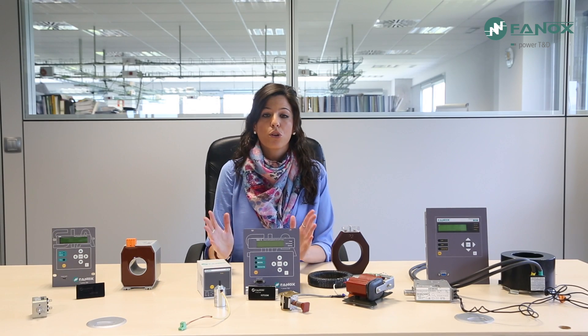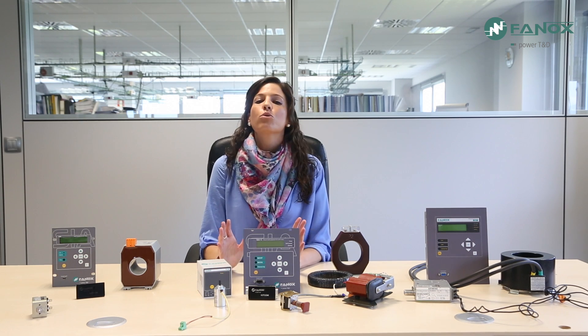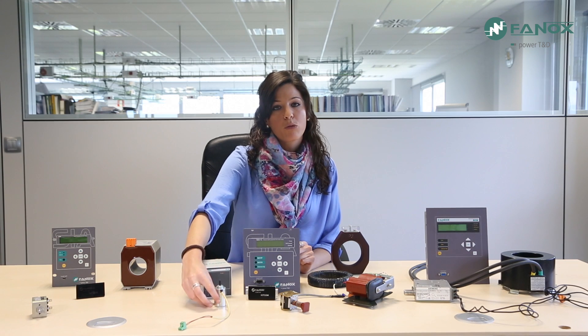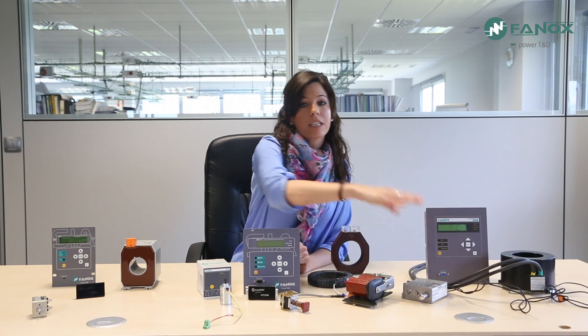Which opening mechanism is used with self-powered relays? Self-powered relays power themselves from primary current, so energy is scarce and efficient energy management is essential. Using coils is not viable due to their very high electrical consumption. Instead, strikers are used. A striker is a simple element consisting of an electromagnet that is charged when the breaker is closed. To trip, it requires low energy — approximately 100 millijoules. The most complicated aspect of strikers is their correct selection, as the market offers a wide range from simple 6-volt strikers up to more complex 24-volt strikers. Correct selection of the striker is therefore essential.